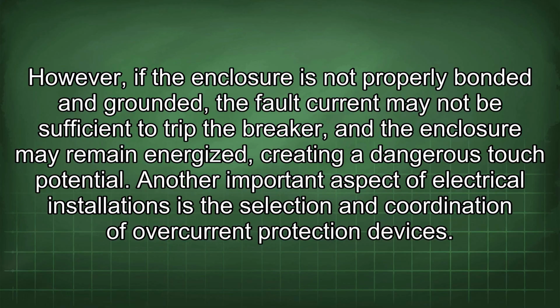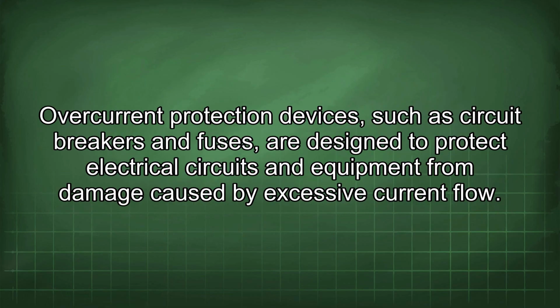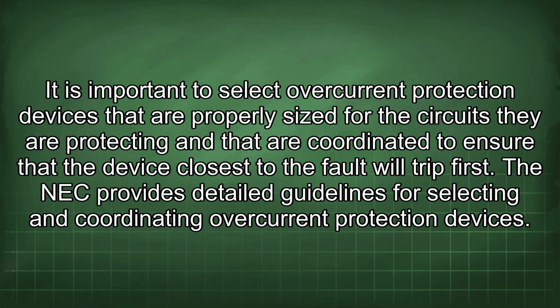Another important aspect of electrical installations is the selection and coordination of overcurrent protection devices. Overcurrent protection devices, such as circuit breakers and fuses, are designed to protect electrical circuits and equipment from damage caused by excessive current flow. It is important to select overcurrent protection devices that are properly sized for the circuits they are protecting and that are coordinated to ensure that the device closest to the fault will trip first. The NEC provides detailed guidelines for selecting and coordinating overcurrent protection devices.